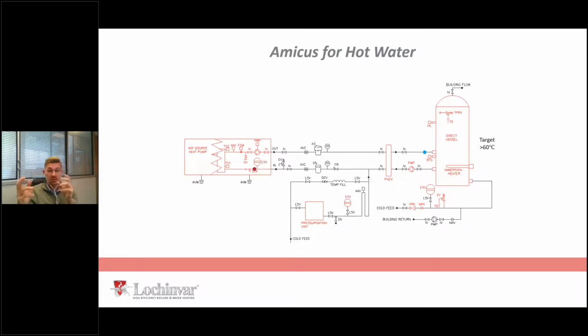Like I said earlier, if you've got an air source heat pump doing hot water, you could fit 2 heat pumps at 66% of the rate each. You probably wouldn't want to fit 2 at 100% of the load. If you fit 2 at 100% of the load, it's quite a big capital investment for something that's there doing nothing for a long period of time. So typically what we would do is 50 kilowatt heat pump, 1,000 litre storage vessel, 50 kilowatt immersion heater. And that way your initial capex comes down significantly. The heat pump is still doing all of the load. The immersion is just there in an emergency scenario. So it's your second point of failure. It's your resilience for the system. It's your business critical hot water still on, and the building still gets to function. The user isn't affected.